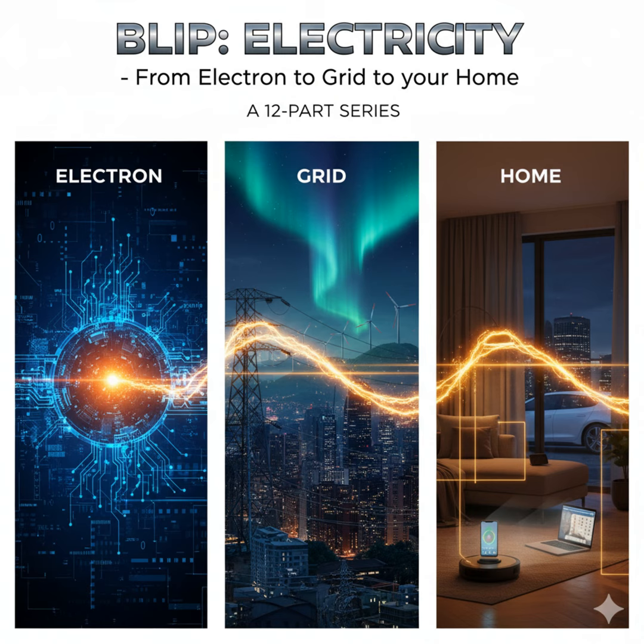Are they just always on? They can be fixed, meaning always connected, or switched. Switched capacitor banks turn on and off in stages, often automatically, based on the measured load or power factor. There are also things like tap-changing transformers or fixed reactors for specific situations, but cap banks are the main tool for lagging PF. And these are good for loads that are relatively stable. Yeah, they're great for handling predictable changes in load over, say, seconds or minutes. Think of a factory floor where large machines turn on and off. They're cost-effective, reliable, standard technology.